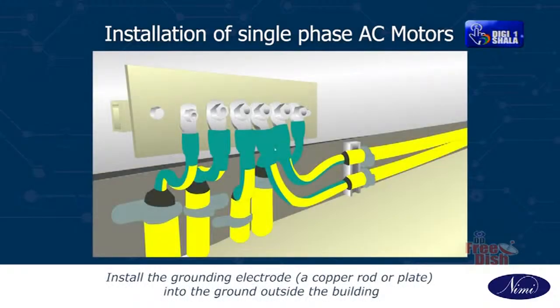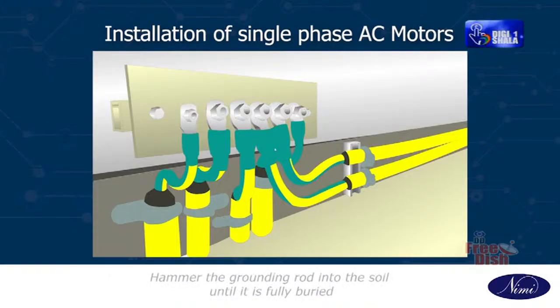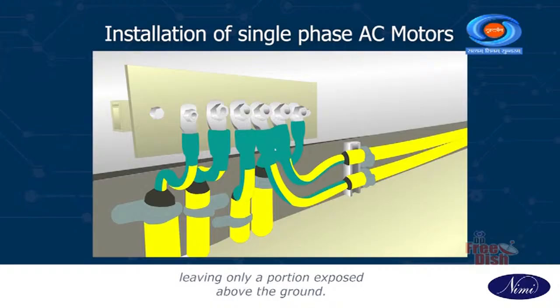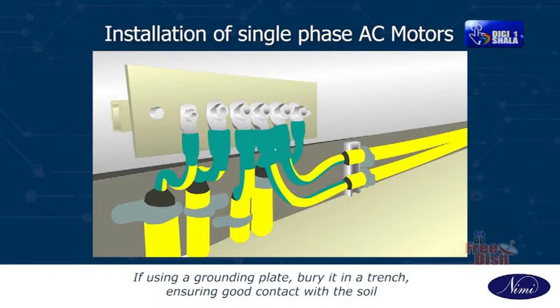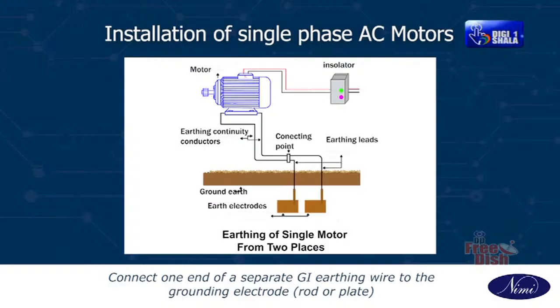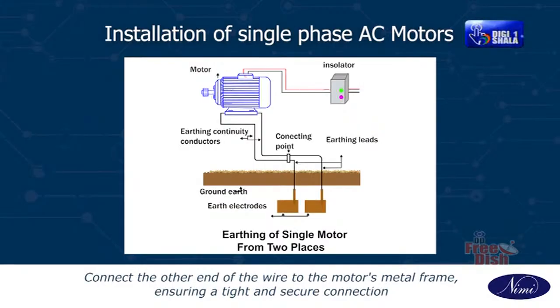Install the grounding electrode, a copper rod or plate, into the ground outside the building. Hammer the grounding rod into the soil until it is fully buried, leaving only a portion exposed above the ground. If using a grounding plate, bury it in a trench, ensuring good contact with the soil. Connect one end of a separate GI earthing wire to the grounding electrode, rod or plate. 7. Connect the other end of the wire to the motor's metal frame, ensuring a tight and secure connection.